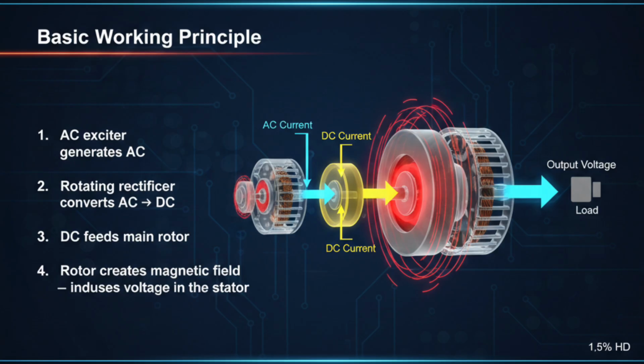Step 3. The DC energizes the main rotor's field windings. The rotating magnetic field induces voltage in the stator windings. The animated 3D flux lines on the slide illustrate this magnetic flux clearly. Step 4. The induced voltage in the stator is supplied to the load. Meanwhile, the AVR monitors the voltage and adjusts excitation to keep it stable.